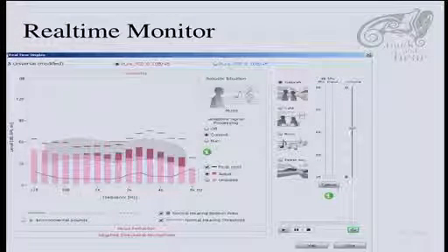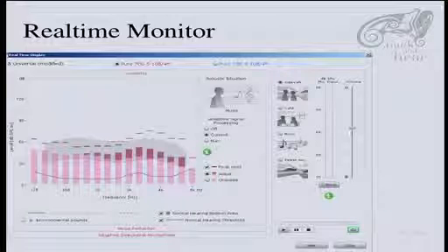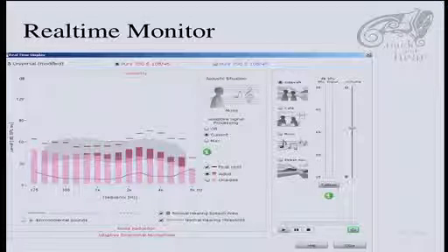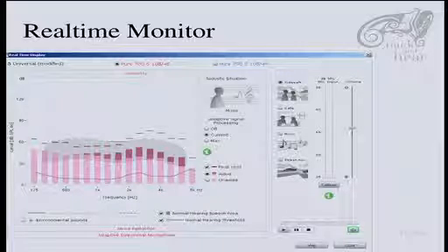The tuning software for hearing aids also has a real-time monitor where you can see some parameters. So you wear your hearing aids and, for example, listen to music, and you can see here the dark areas are where the hearing aid actually started to work. Below that, it doesn't need to amplify, and the gray thing here is the speech banana. So you see that it's optimized in a way that it starts amplifying in the speech banana.